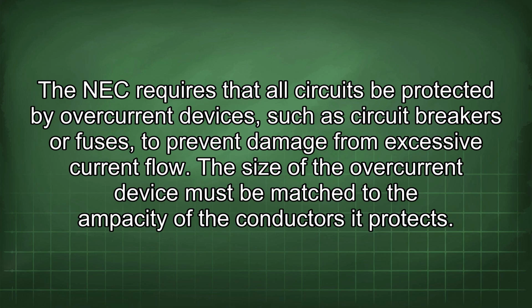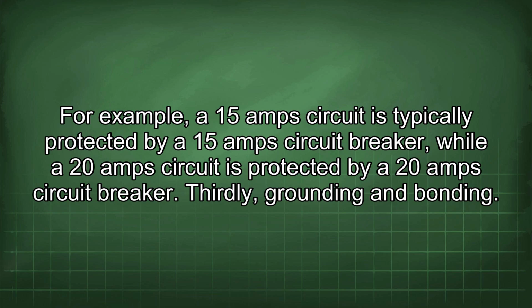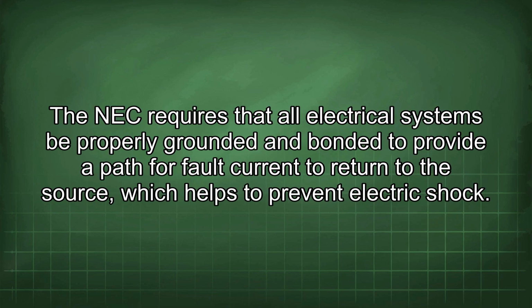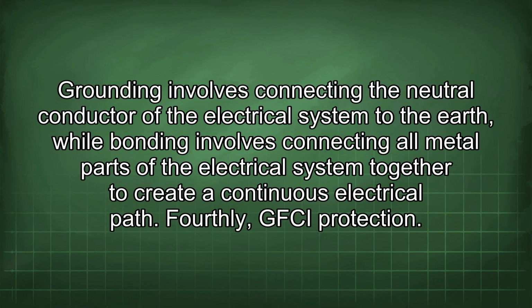The NEC requires that all circuits be protected by overcurrent devices, such as circuit breakers or fuses, to prevent damage from excessive current flow. The size of the overcurrent device must be matched to the ampacity of the conductors it protects. For example, a 15 amp circuit is typically protected by a 15 amp circuit breaker, while a 20 amp circuit is protected by a 20 amp circuit breaker. Thirdly, grounding and bonding. The NEC requires that all electrical systems be properly grounded and bonded to provide a path for fault current to return to the source, which helps to prevent electric shock. Grounding involves connecting the neutral conductor of the electrical system to the earth, while bonding involves connecting all metal parts of the electrical system together to create a continuous electrical path.